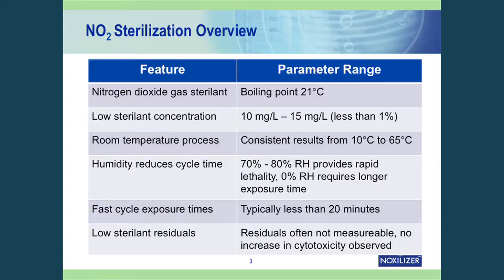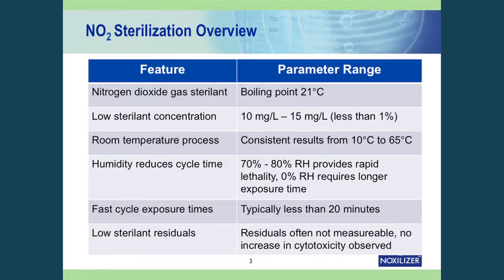With the 70 to 80% relative humidity cycle, the exposure time for a load of medical devices is 20 minutes. The door-to-door time for the sterilizer might be closer to an hour or an hour and a half because of evacuation, filling, pumping, aeration, and the other processes in the cycle. The nitrogen dioxide has a very high vapor pressure and does not condense on surfaces, which reduces the cytotoxicity measured. When we do biocompatibility testing on products exposed to our process, we don't see an increase in cytotoxicity, due to the efficient removal of sterilant residuals.